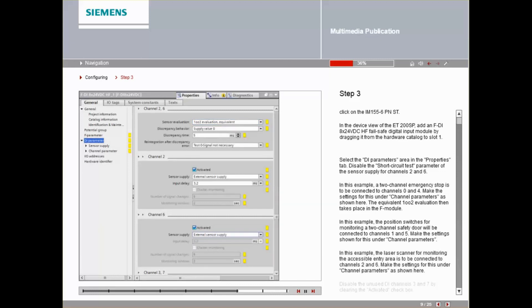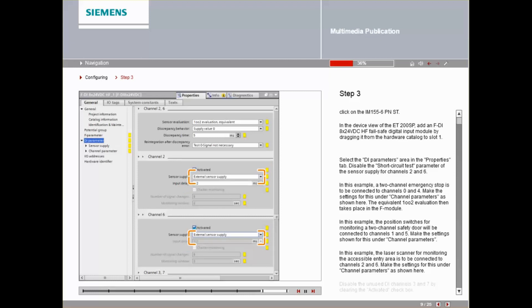In this example, the laser scanner for monitoring the accessible entry area is to be connected to channels 2 and 6. Make the settings for this under Channel Parameter as shown here. Disable the unused DI channels 3 and 7 by clearing the Activated checkbox.